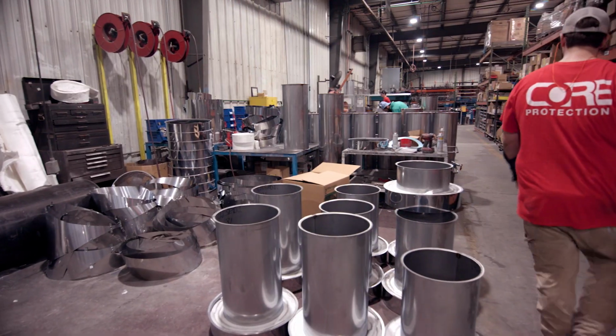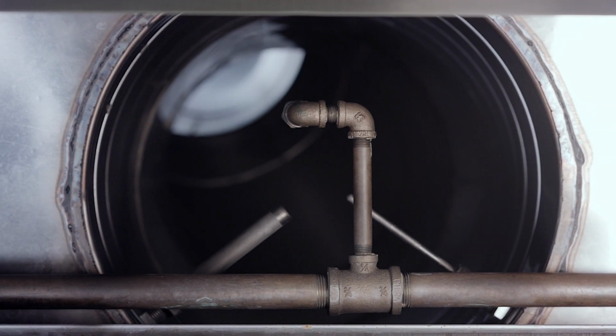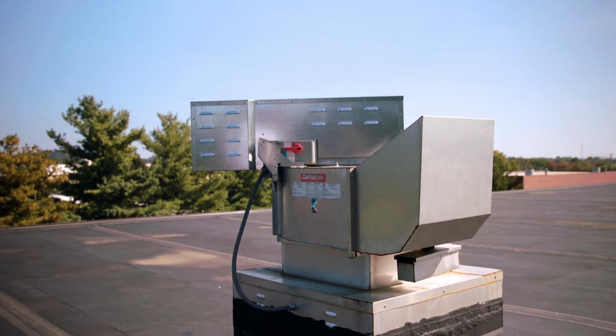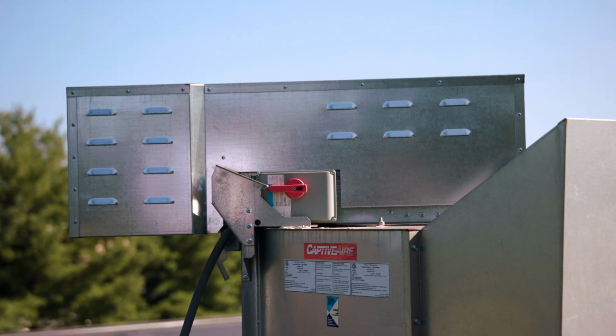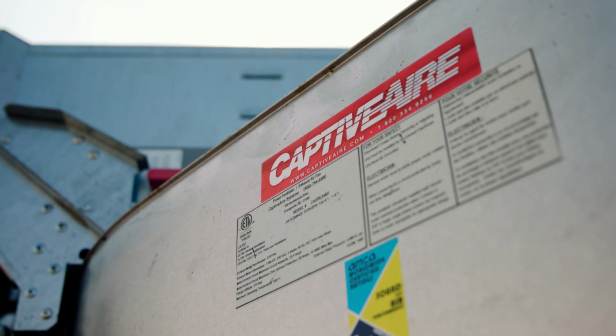With solid fuel appliances, there's a lot of heat in the ductwork to manage. We see temperatures in excess of 200 degrees very often, and this heat is exposed right to the fan. So we have utility sets with steel wheels and direct drive motors specifically designed for solid fuel cooking appliances.